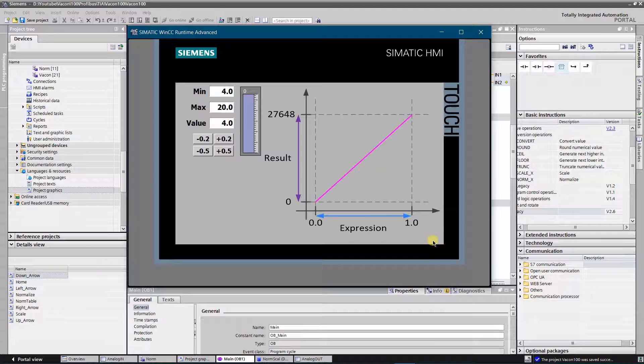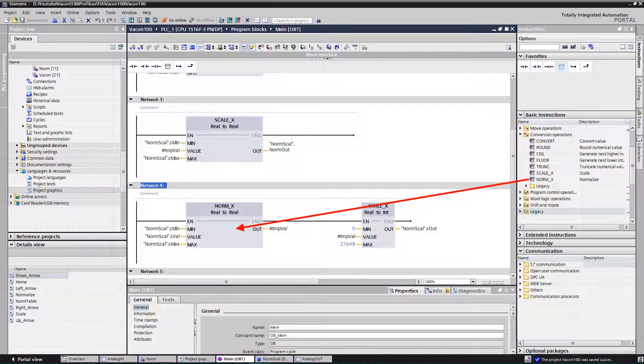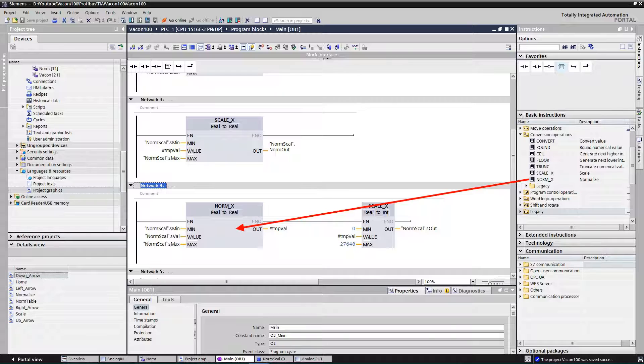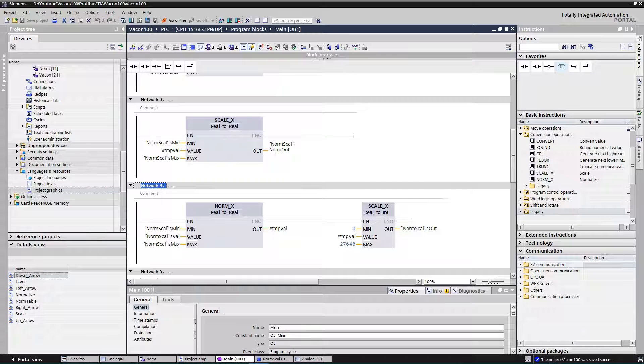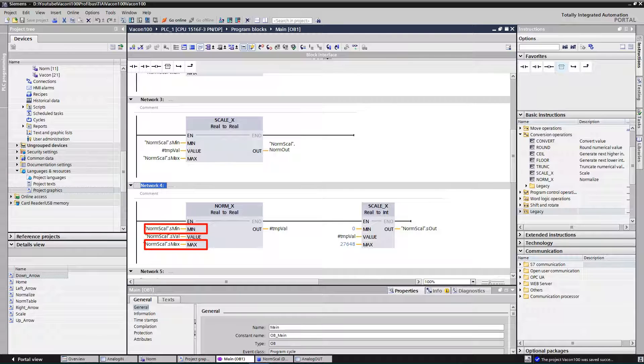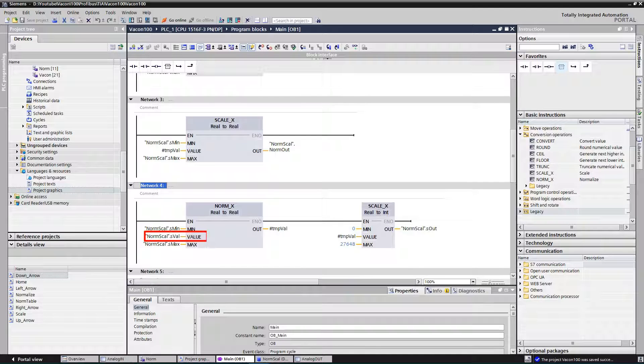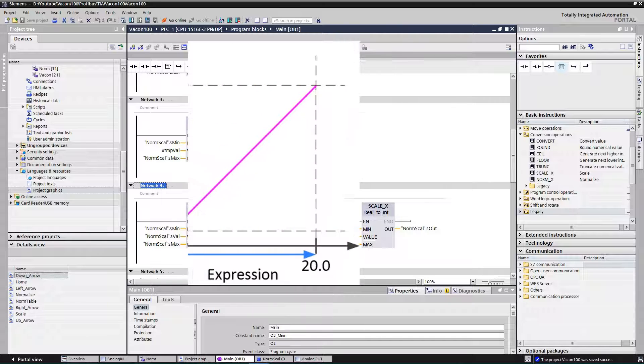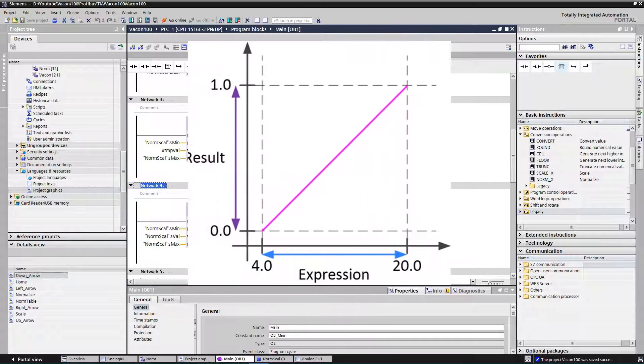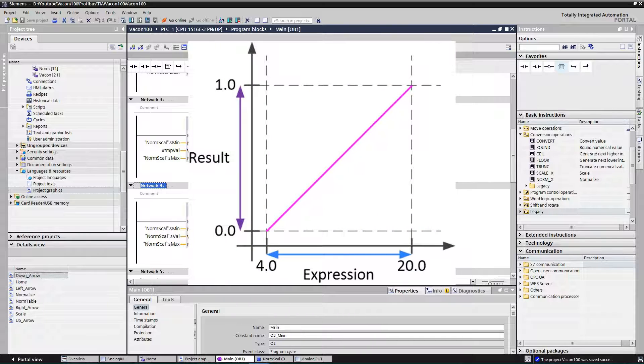Let's go to the programming part. Drag and drop instruction NORM_X from library to the network. This example will be based on the analog signal of 4 to 20 milliamps, with the possibility to change the limits dynamically. Assign floating point tags to the inputs min and max. At the input named value, assign your setpoint tag. Instruction will generate result, which value will be within 0 and 1.